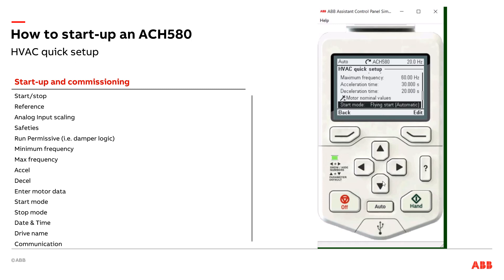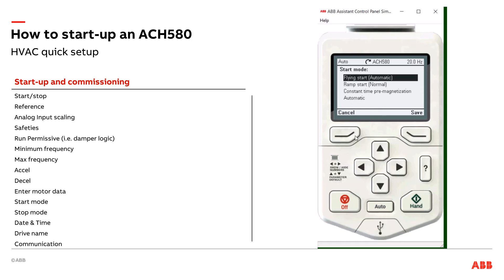Next item is your start mode. Usually this will be left at flying start automatic — that's where if the motor's still spinning, the drive can catch it and pick it up and ramp it to where you need it to go. Not necessarily needed for a pump application, so you could adjust that to ramp start. But if you left it at flying start for a pump, not a problem.